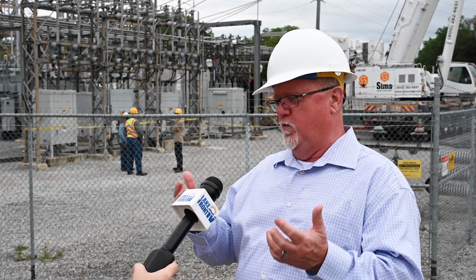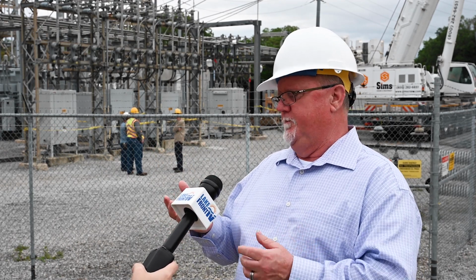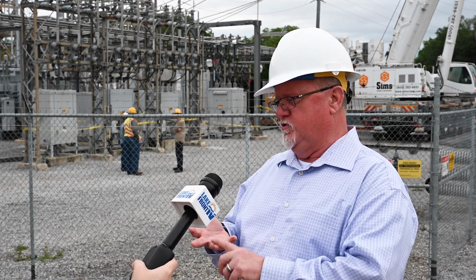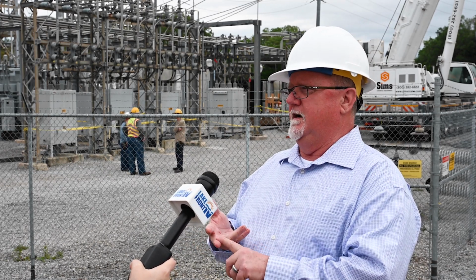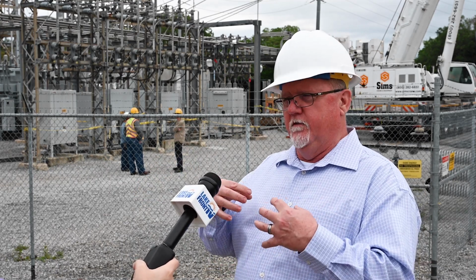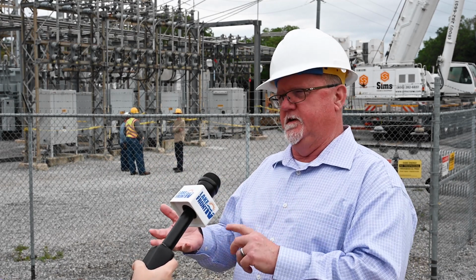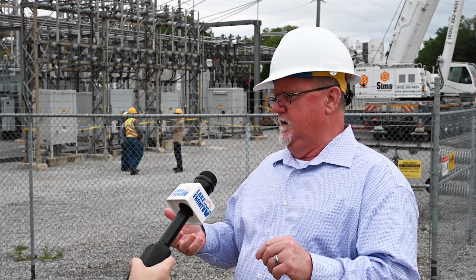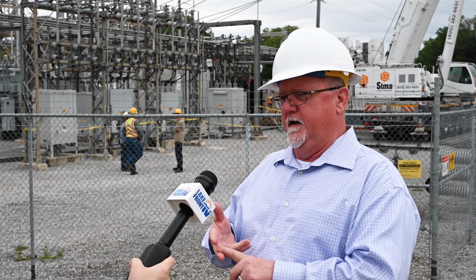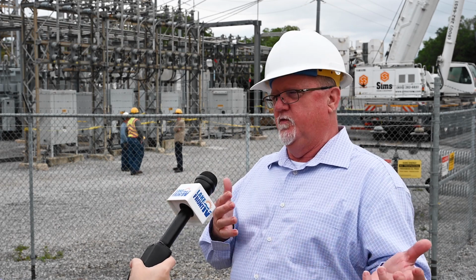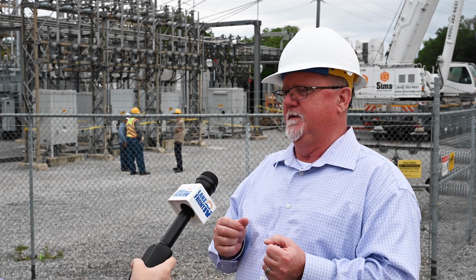If you imagine, the technology that was put in 44 years ago has advanced a lot. So we're going to use this opportunity to upgrade our system protection and control wiring, have more control and more telemetry on the unit, so we'll know the temperature, the loading factor, and when it looks like there may be an issue we need to address. It's really about upgrading the whole process during this project.